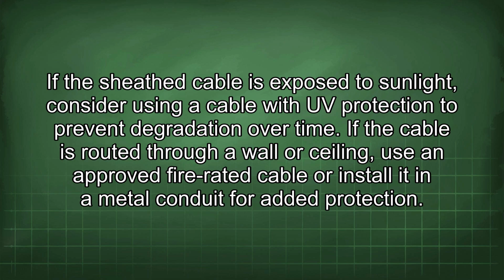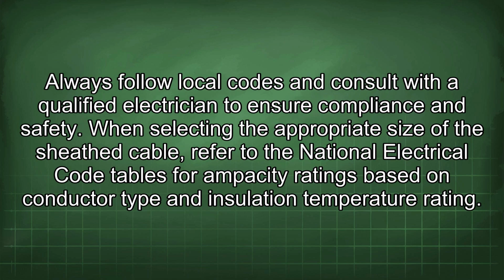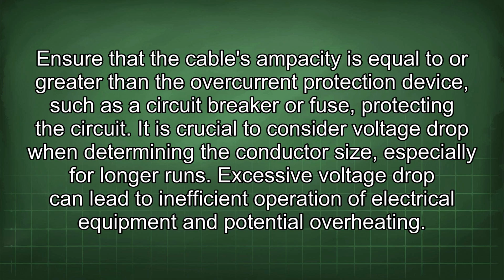If the cable is routed through a wall or ceiling, use an approved fire-rated cable or install it in a metal conduit for added protection. Always follow local codes and consult with a qualified electrician to ensure compliance and safety. When selecting the appropriate size of the sheathed cable, refer to the National Electrical Code tables for ampacity ratings based on conductor type and insulation temperature rating. Ensure that the cable's ampacity is equal to or greater than the overcurrent protection device, such as a circuit breaker or fuse protecting the circuit.